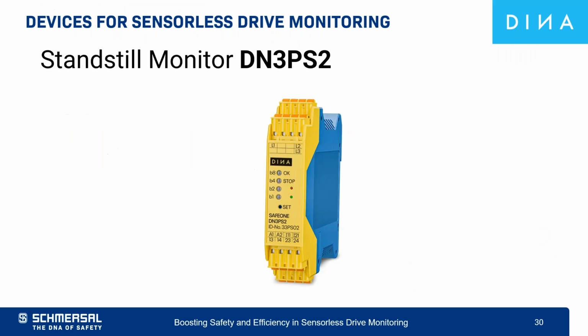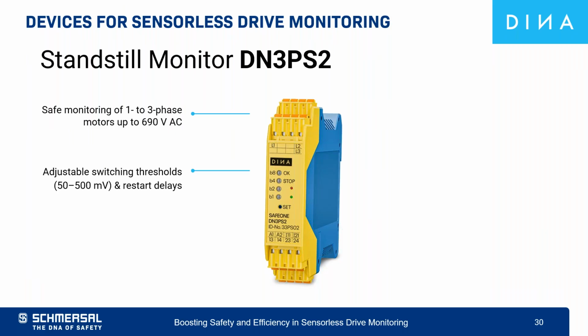The next compact module out of our portfolio, which I would like to tell you more about, is the DN3PS2, the standstill monitor. It can be used for the same type of motors as the speed monitor. It also has the same form factor. It can be parameterized, but you don't need the software to do the parameterization. You can parameterize the switching thresholds between 50 to 500 millivolt and restart delays. And to do the parameterization, there's a set button you can see here on the front panel of the unit.